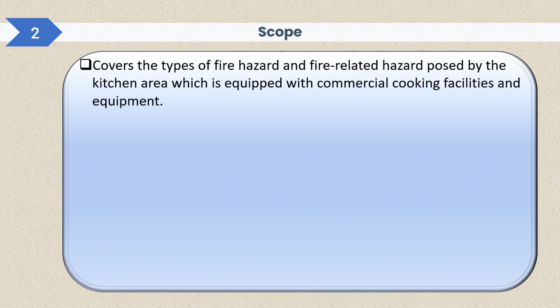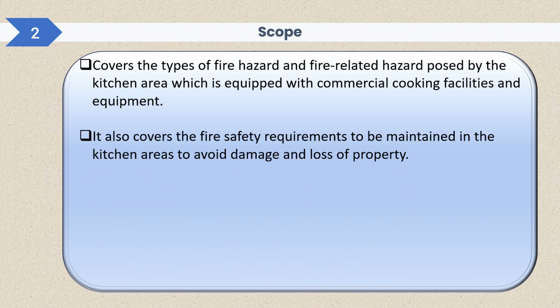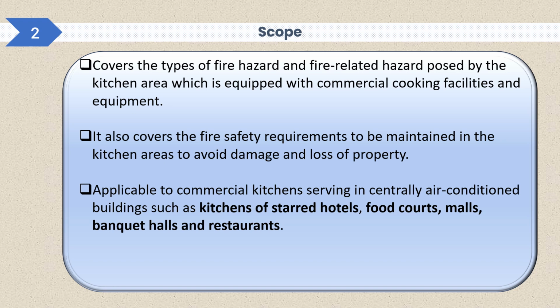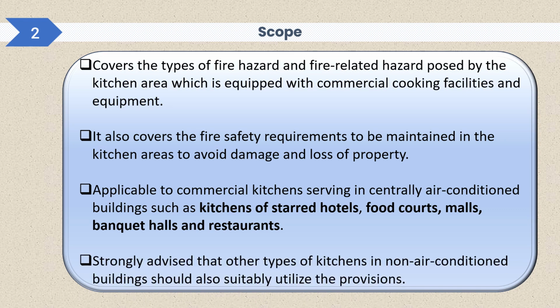So what is the scope of this standard? It covers the types of fire-related hazards posed by the kitchen area which is equipped with commercial cooking facilities and equipment. It also covers the fire safety requirements to be maintained in the kitchen areas to avoid damage and loss of property. It is applicable to commercial kitchens serving in centrally air conditioned buildings. I would repeat this: centrally air conditioned buildings such as kitchens of starred hotels, food courts, malls, banquet halls and restaurants. It is also strongly advised by this standard that other types of kitchens in non-air conditioned buildings should also suitably utilize these provisions.